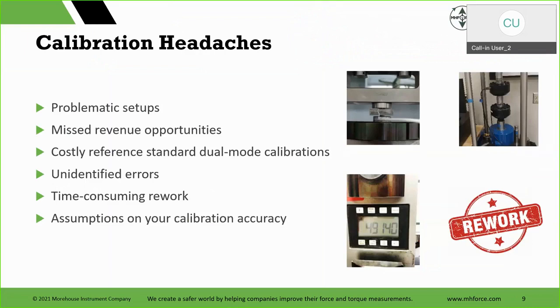Unidentified errors. Hey, I have a technician that's making measurements. They think they're good to go. They've done 4 weeks of measurements, and then you find out, no, this device should be loaded through top and bottom threads every single time. That's how it's designed. That's how it's to be used in the field. This is where we can help with guidance. This is where, talking to your customer, understanding and replicating use.